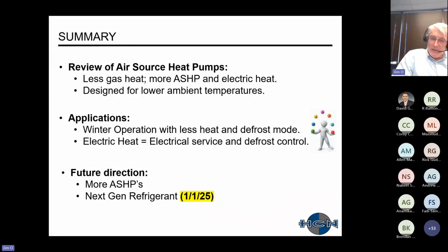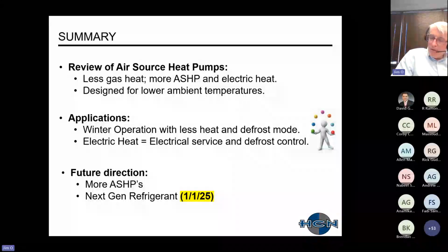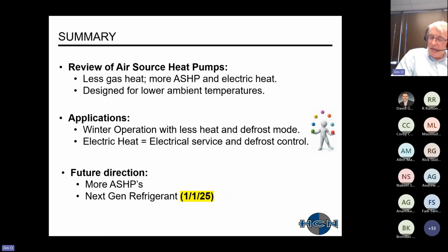And then once again, I want to emphasize that 410A is being phased out on deliveries of new equipment on January 1st, 2025. That's associated with, I'll call it, rooftop units and items with scroll compressors: rooftop units and split systems, 1-to-1 or 2-to-1 split systems. It would be applicable to chillers, but I feel like the world of chillers has already migrated to the new refrigerants, so it's not applicable. And I also want to point out that the refrigerant conversion for VRF systems was granted an additional year for the phase out. So the VRF phase out is 1/1 of 26.